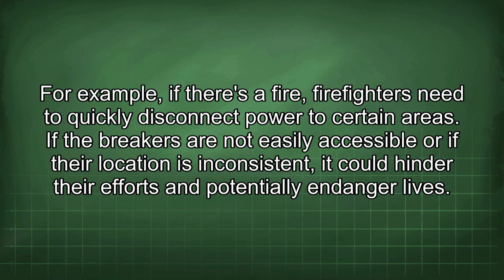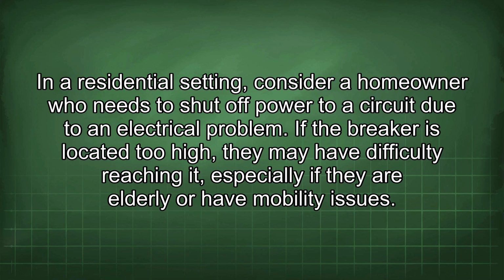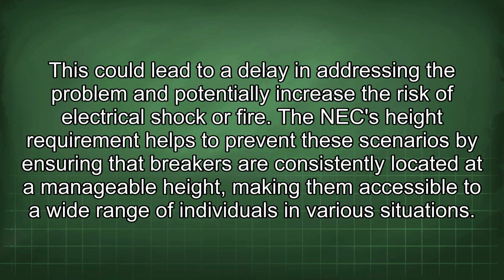In a residential setting, consider a homeowner who needs to shut off power to a circuit due to an electrical problem. If the breaker is located too high, they may have difficulty reaching it, especially if they are elderly or have mobility issues. This could lead to a delay in addressing the problem and potentially increase the risk of electrical shock or fire. The NEC height requirement helps to prevent these scenarios by ensuring that breakers are consistently located at a manageable height, making them accessible to a wide range of individuals in various situations.